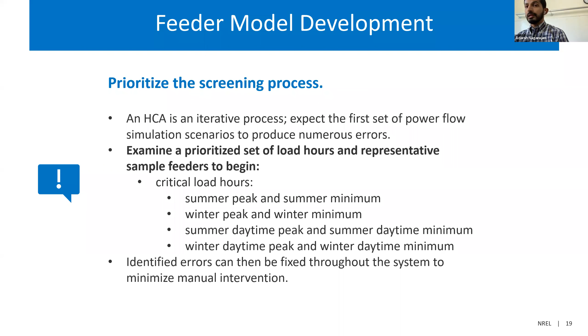Say you have a model already converted into your appropriate tool or software. You want to simulate them to make sure the feeder is accurate. You need to prioritize the screening process, which means it's not wise to run chronologically from Jan 1st to December 31st for all 1,000 feeders and then look at the errors. It's better to look at the critical load hours and fix the issues. Critical load hours may be summer peak, summer minimum, springtime maybe, which has low load and high solar. All these scenarios should be simulated first on the baseline feeder without adding any additional solar, for what exists as of now. Then make sure you look at the key parameters, which you will look at in the next slide.